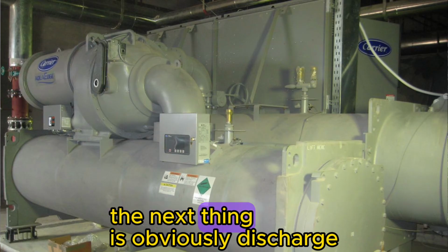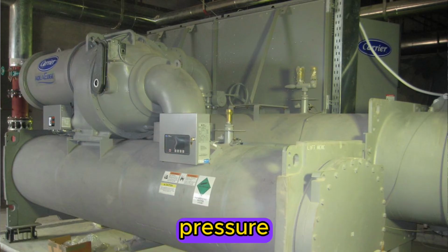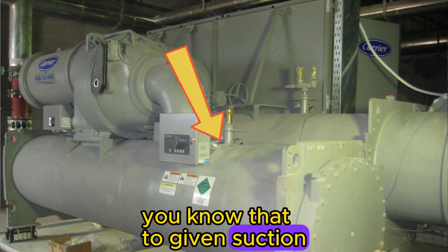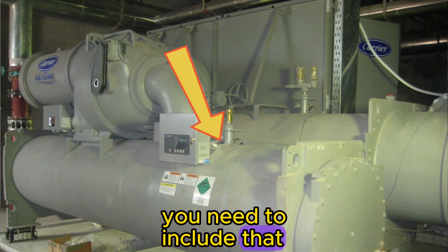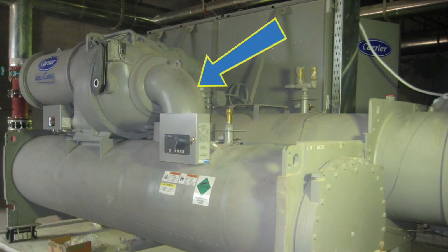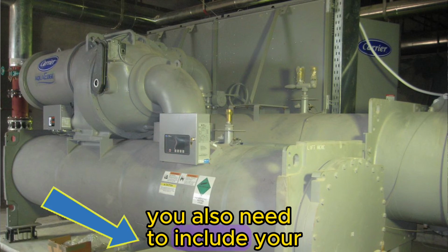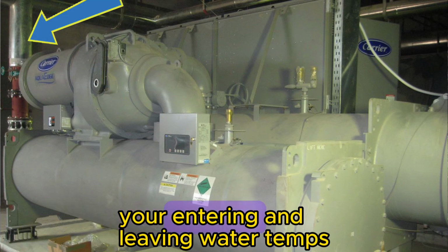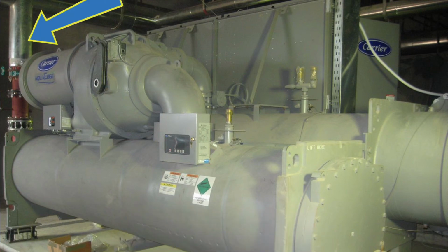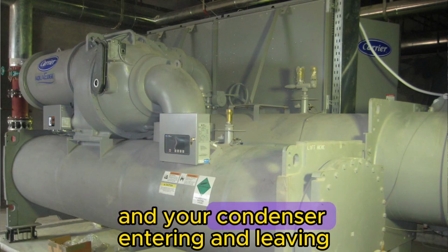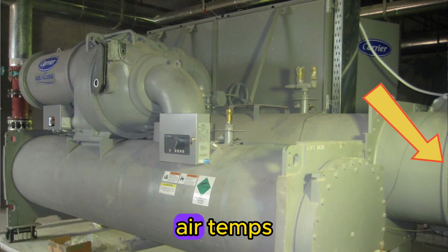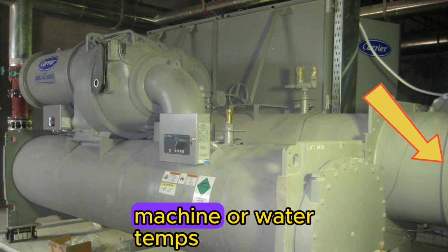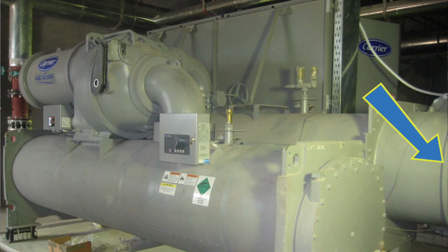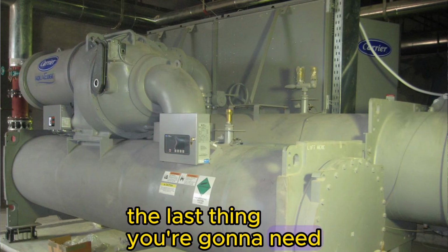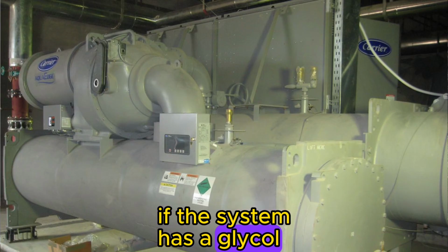The next thing is obviously discharge pressure. That's a given. Suction pressure, you need to include that. You need to include suction superheat. You also need to include your subcooling, your entering and leaving water temps, and your condenser entering and leaving air temps if it's an air-cooled machine, or water temps if it's a water-cooled machine. The last thing you need to give is whether the system has glycol or not.